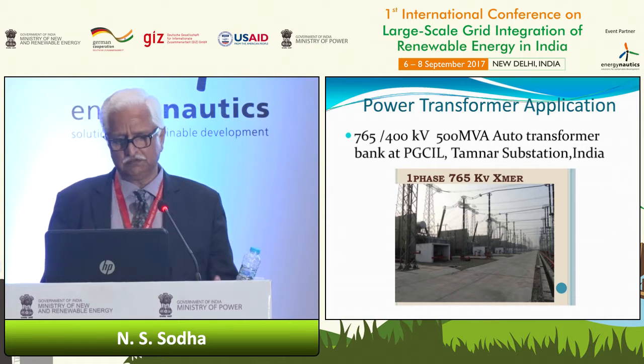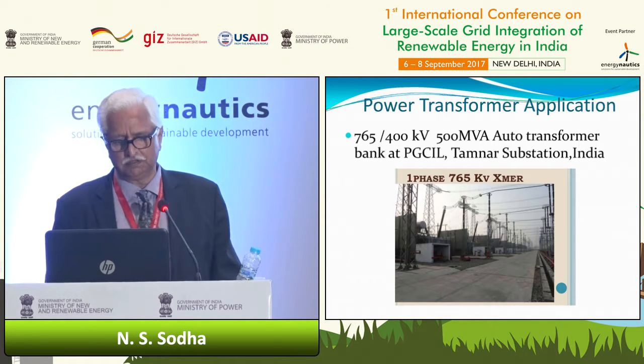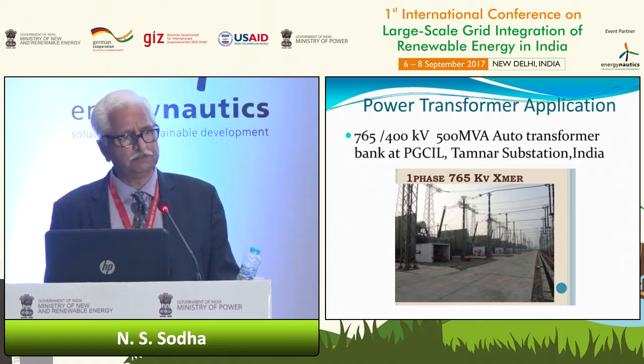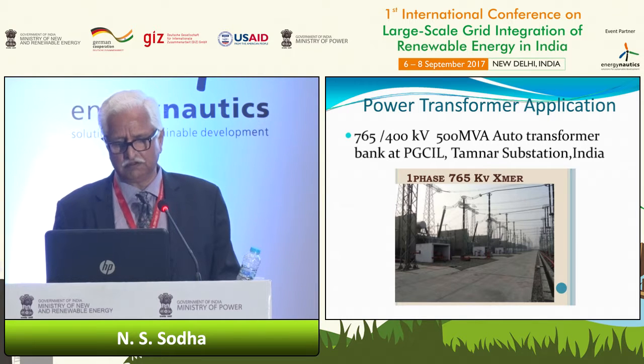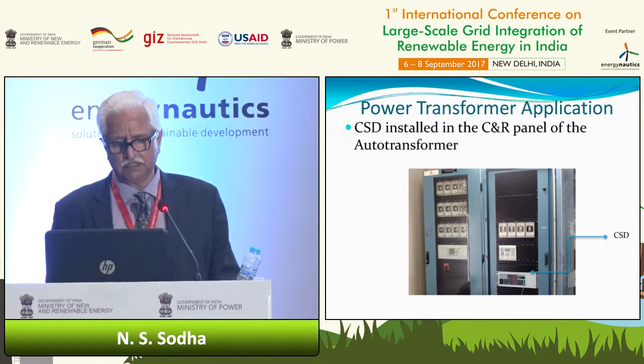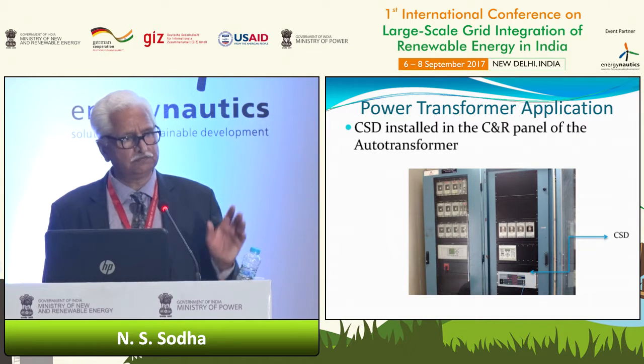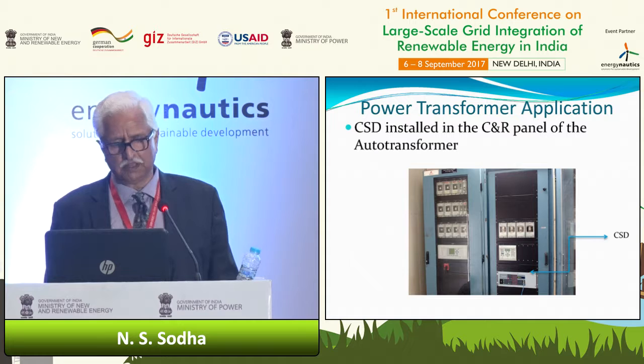We have some experience to share from the power transformer application at Power Grid, at a 765 kV, 500 MVA transformer at a Tamnar Substation. And you can see here, this control switching device fits into the panel of the transformer or in the control room very easily, and it can be retrofitted very easily.